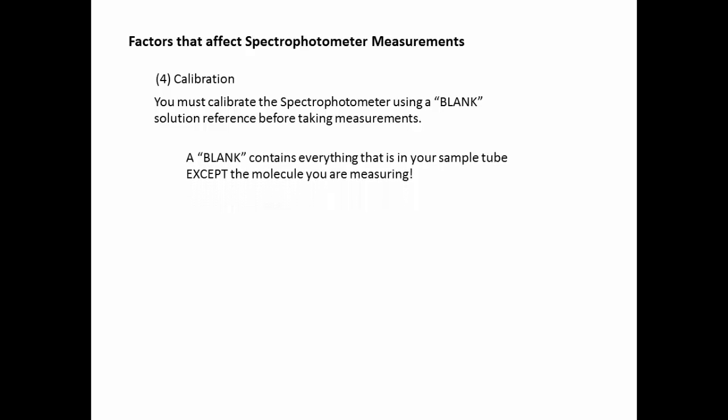Another thing that affects spectrophotometer measurements is calibration. You must not forget to calibrate the spectrophotometer before using it like any measurement device. And we use something called a blank solution as a reference in order to zero out and set the maximum measurement value for calibration. A blank solution contains everything that is also in your sample tube, and also in the same amounts. The only thing it does not contain is the molecule you're trying to measure.